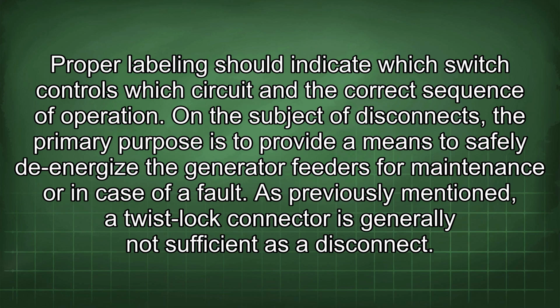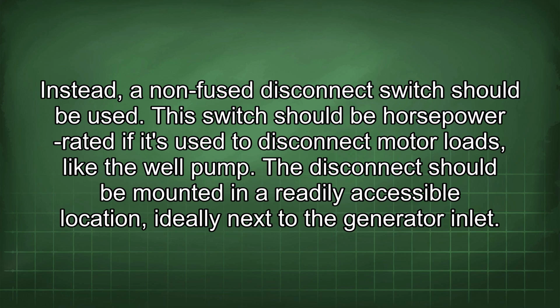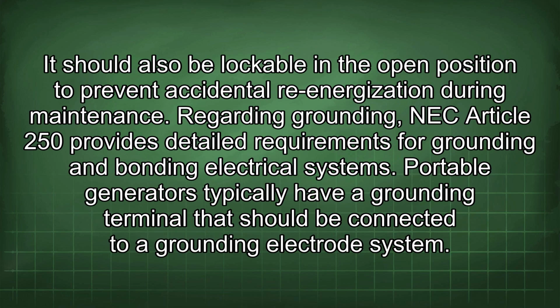On the subject of disconnects, the primary purpose is to provide a means to safely de-energize the generator feeders for maintenance or in case of a fault. As previously mentioned, a twist lock connector is generally not sufficient as a disconnect. Instead, a non-fused disconnect switch should be used. This switch should be horsepower rated if it's used to disconnect motor loads, like the well pump. The disconnect should be mounted in a readily accessible location, ideally next to the generator inlet. It should also be lockable in the open position to prevent accidental re-energization during maintenance.